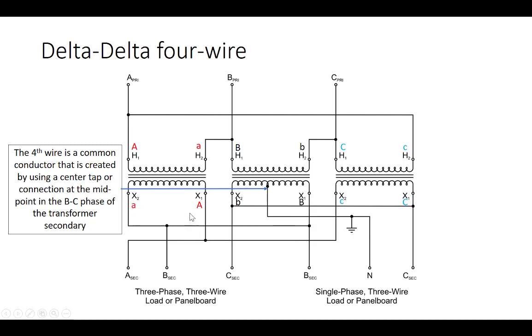The lines A, B, and C come off of X1 on the secondary windings of these transformers, and the end of each winding connects to the beginning of the second winding. End of A phase connects to the beginning of B phase, end of B phase connects to the beginning of C phase, end of C phase is connected back to the beginning of A phase.